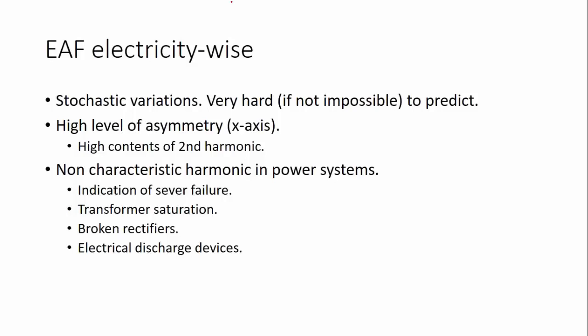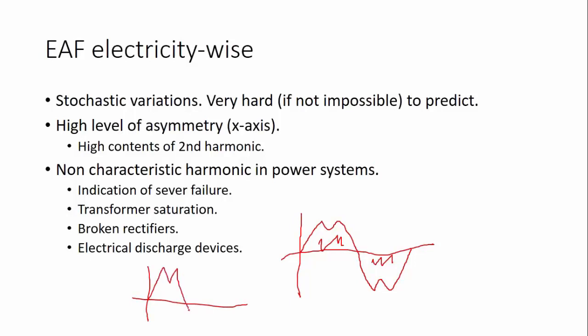So one of the main characteristics of the arc is that it's highly asymmetrical with respect to the x-axis. Even though you may have a high degree of distortion, in a normal load you can have x-axis symmetry. But in an arc furnace, you can have a very asymmetrical load, which can be something like this. This has a high degree of asymmetry. When you have asymmetry with respect to the x-axis, you have second harmonic.